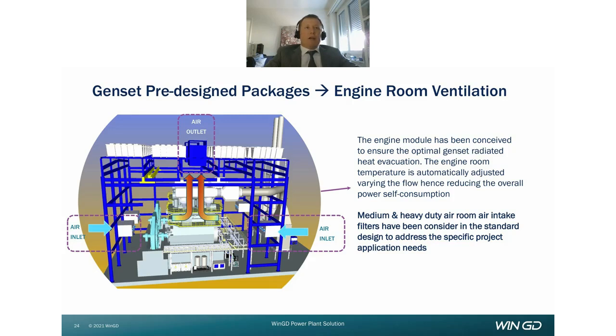The genset module ventilation path has been designed to ensure a very efficient radiated heat removal and avoid hot pockets. The fresh air is drawn in on both sides of the genset room, and it's evacuated through the outlet box fitted across the roof. The air inlet boxes include a filtration chamber provision should the plant be operated in a dusty environmental condition. Both the air inlet and the outlet boxes are designed with louvers and dampers to seal the genset room in case of fire and avoid dust ingress while the genset is standstill.